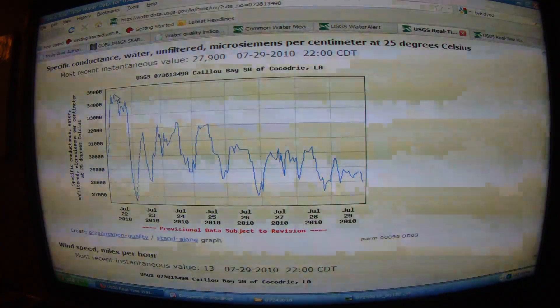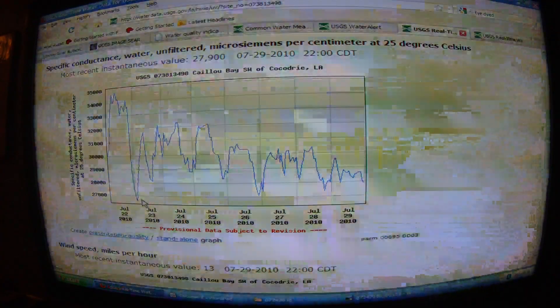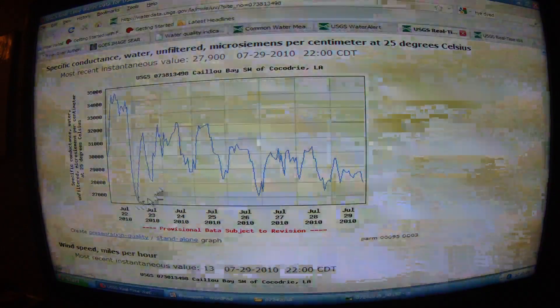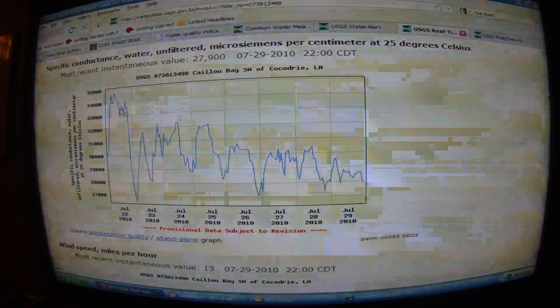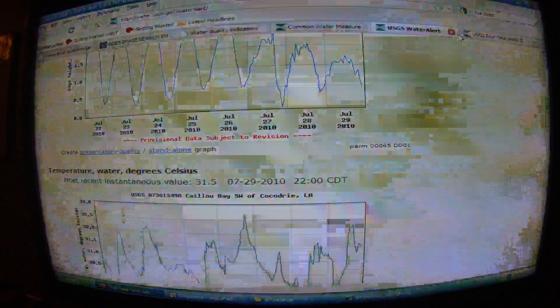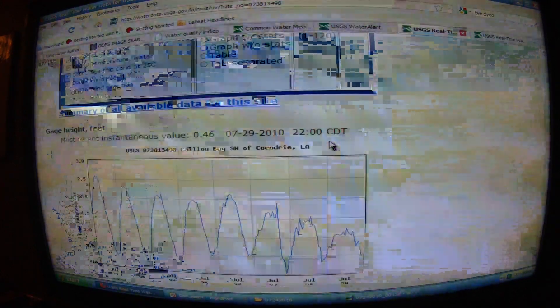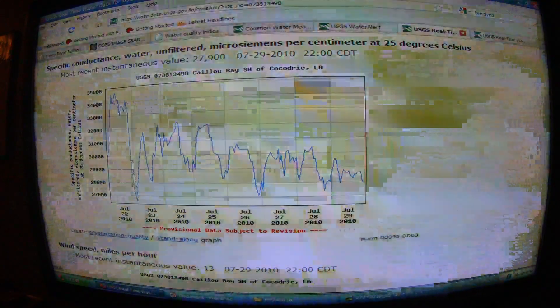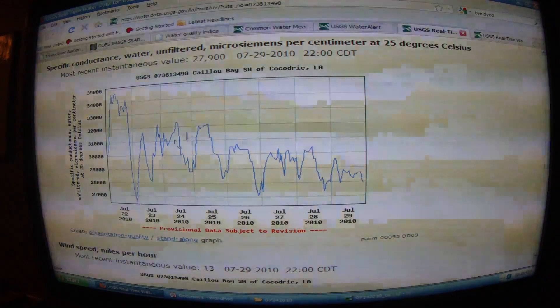Earlier in the week it was up around 34,500 micro siemens. Even if we say the Lower Colorado River Authority's expected level could be double or triple — say 2,100 instead of 700 — 34,500 is still extreme. On a daily basis, specific conductivity is varying between as low as 26,000 and as high as 34,500. The variation alone on a daily basis shows why continuous testing is so critical.